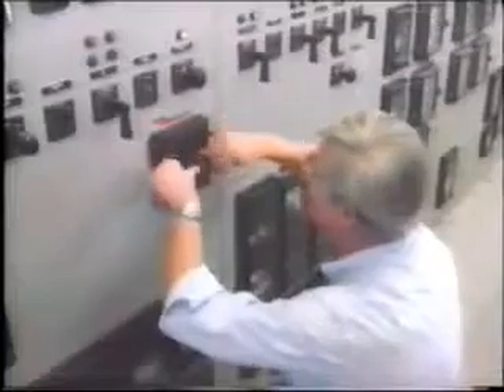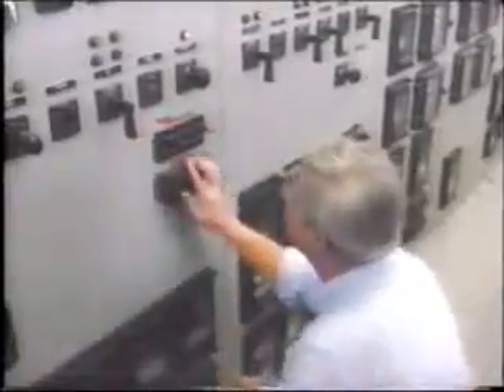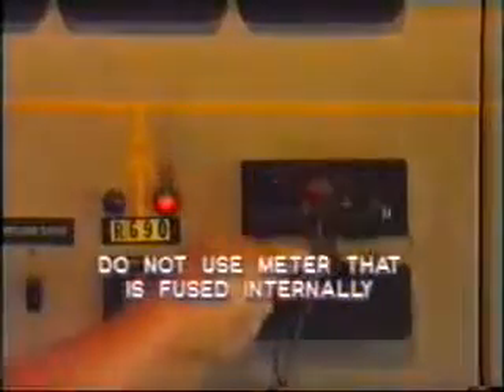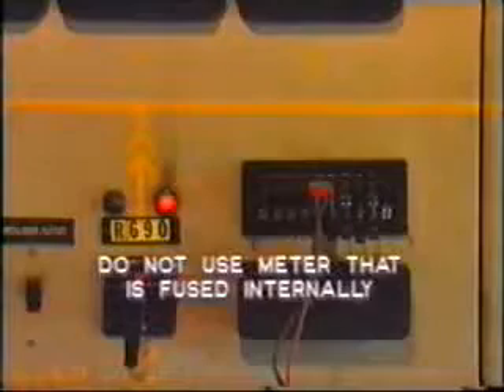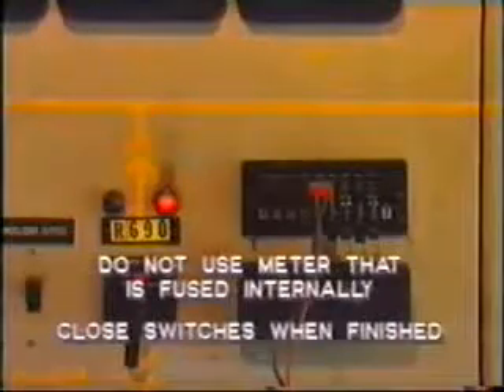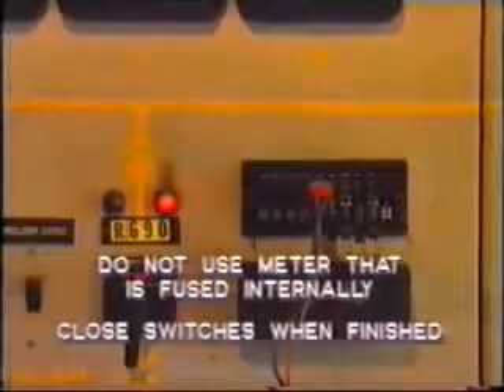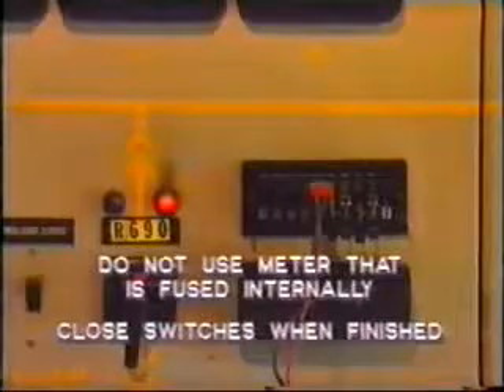With current transformers, we have an opposite problem to the VT. We must remember to never open circuit the secondary of an energized current transformer. Very high voltage can develop across the open circuit terminals, often above 10,000 volts. Therefore, when you're measuring CT secondary current, be careful not to use any meter which contains an internal fuse. Also, make sure that the CT connection switches are all closed at the relay panel.